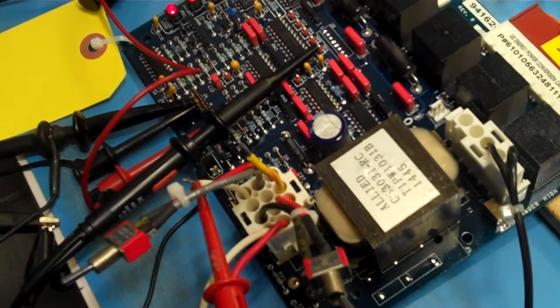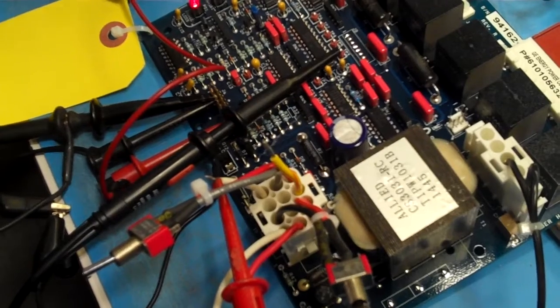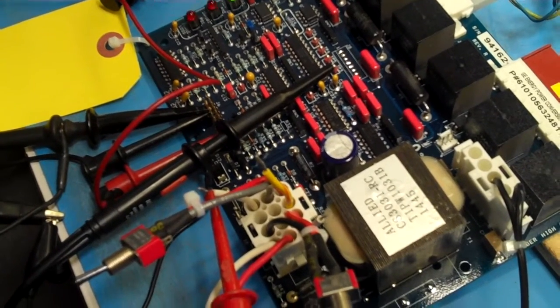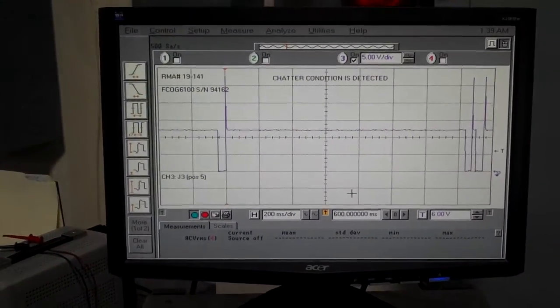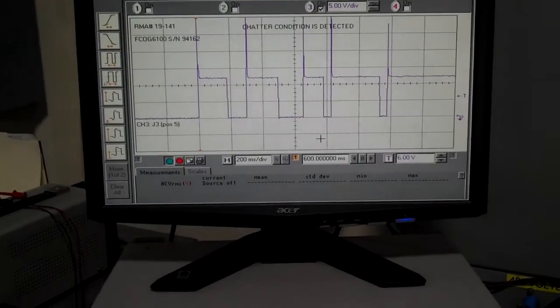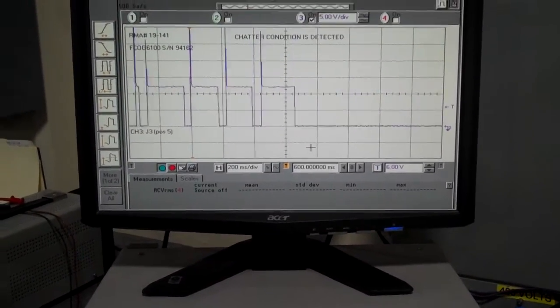and U7. And basically every time that we have this fault, the relay is being energized, de-energized. It's normally energized, now it's de-energized, and we have this chattering condition that we've covered here. This will be the problem experienced with this board.